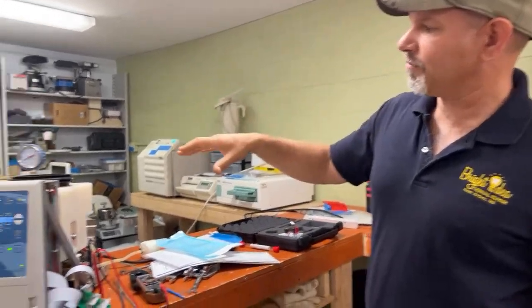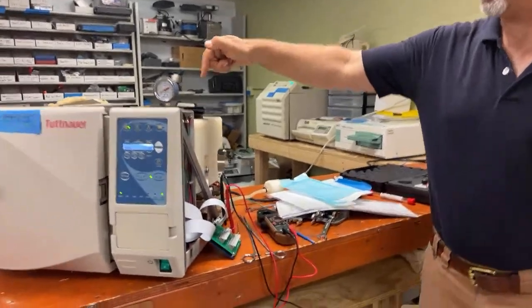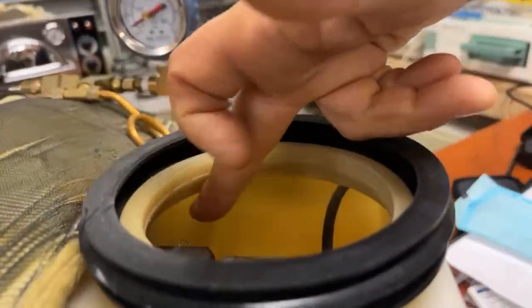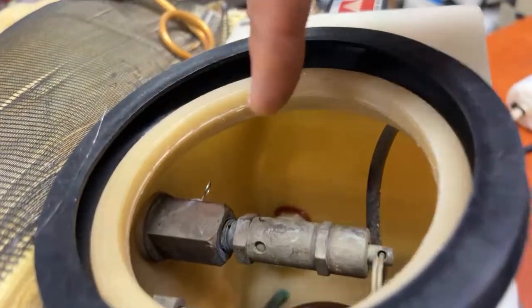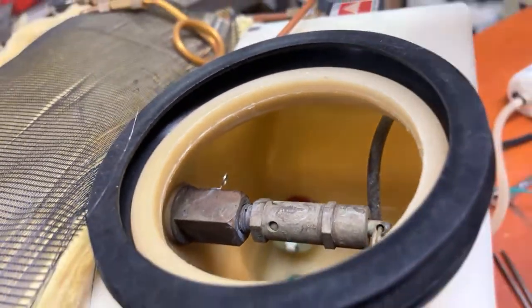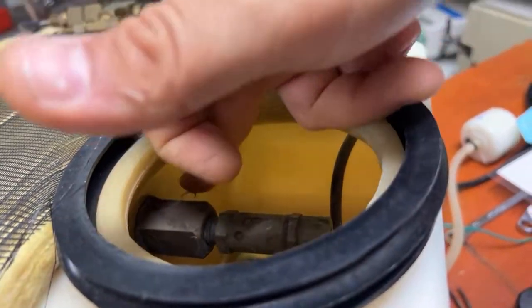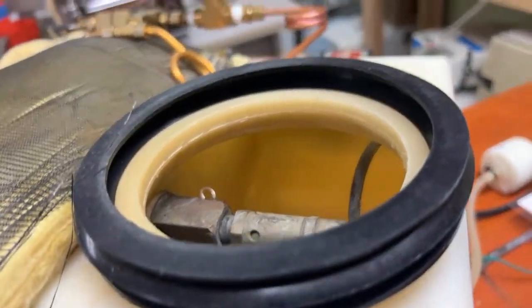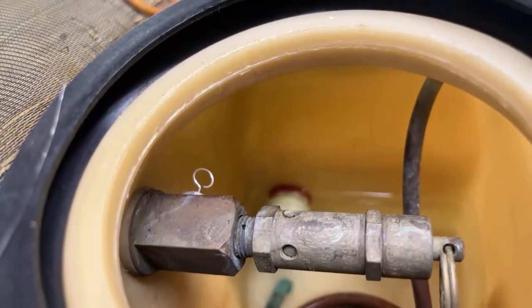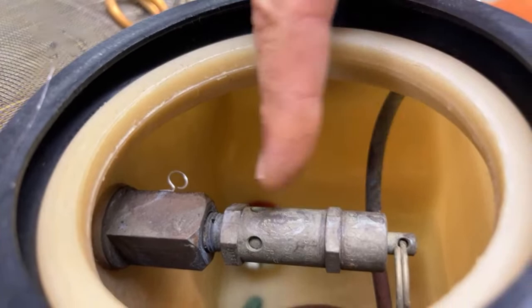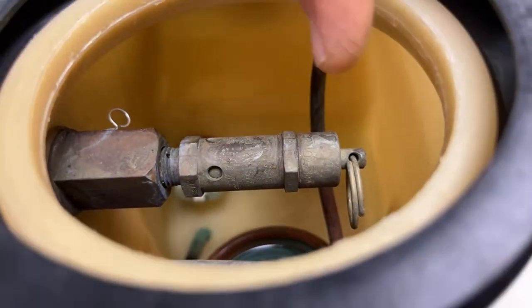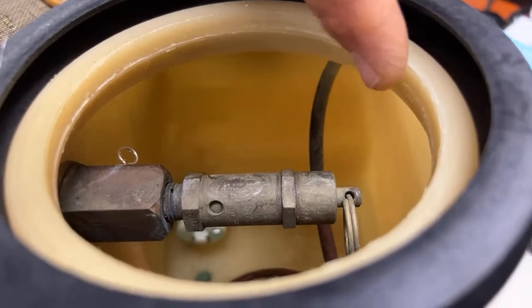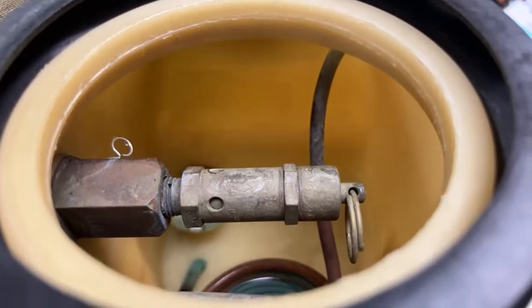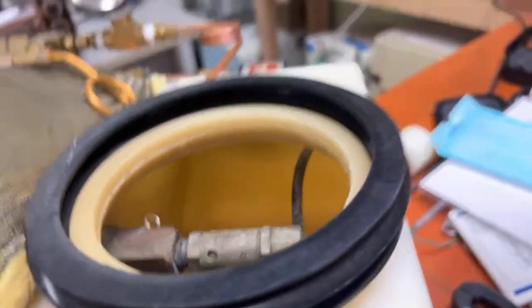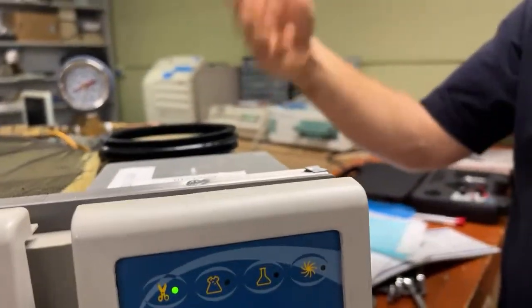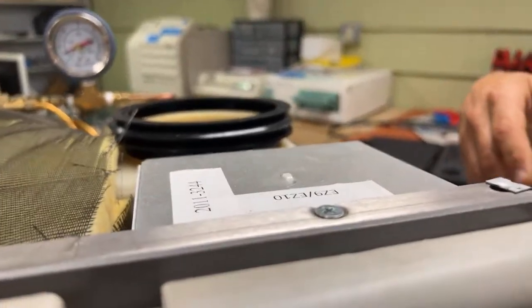Now what's happening is we're starting to get pressure build up, and there's this little pressure vent. It's normal for it to be venting like that. It's designed to be pulled and pushed to clear it temporarily. There's also a safety valve here. One of the things Tuttnauer recommends is to pull that little grenade pin out and test it periodically. I never touch it because once I touch it, it breaks. My thought is, if it's not leaking, if it ain't broke, don't make it broke.